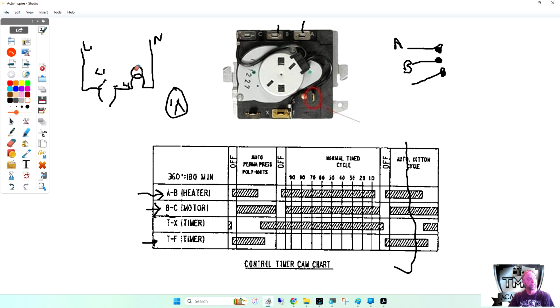Because watch this. What if I'm checking the switch because the light bulb's not working, right? What if the light bulb's broken? On an open switch, what's my reading? 0 volts. Why? Because I can't get back to neutral. If I get a closed switch, what's my reading? 0 volts, because I can't get to neutral. And then if you did that, you would say that that switch is bad, because you got 0 volts on both sides. Something's wrong with that switch, because it's supposed to give me voltage when it's open and no voltage when it's closed, when the problem is my light bulb.